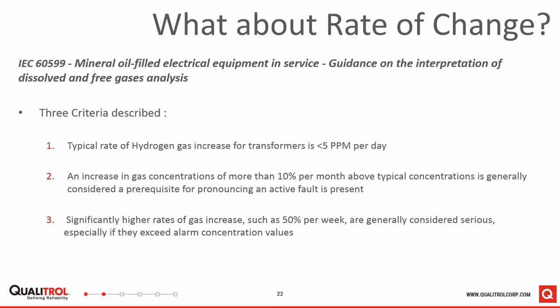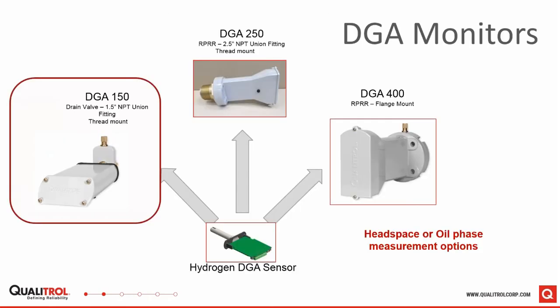that. So we looked at why hydrogen, how much hydrogen, what rate of change of hydrogen. Just a couple of slides now, and we're not far away from the end here. Just a couple of slides on the DGA monitor and the technology in the Qualitrol DGA monitor. So Serveron/Qualitrol have a range of different DGA monitors from single gas up to 8 or 9 gas. What we're looking at here is single gas monitors, and specifically what we're looking at is the monitor that we call DGA150. This is our solution for the vault application.